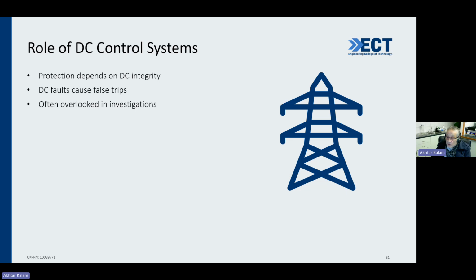So let us look at the role of the DC. I told you about the saturation and the DC offset. When there is unintended leakage or a wiring fault, this can energize the trip coil without any primary fault. DC trip circuits use a DC supply, protective relay contacts, and a trip coil, which initiates the breaker opening. An unintended spurious trip occurs due to insulation degradation, moisture, wiring faults, or bypassed protective circuits and contacts. These issues can be mitigated by monitoring for ground faults and ensuring proper cable insulation.